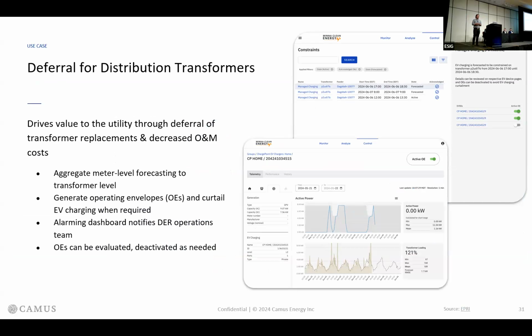This is some work we're executing on to activate managed EV charging to preserve or extend the life of distribution transformers. This doesn't require all the power flow models we looked at in the last slide. It can just be aggregation of forecasted meter loads up to that transformer level, to understand the remaining capacity and how much EV charging is available, and when you may need to curtail some to avoid excessive overloading for extended periods of time.